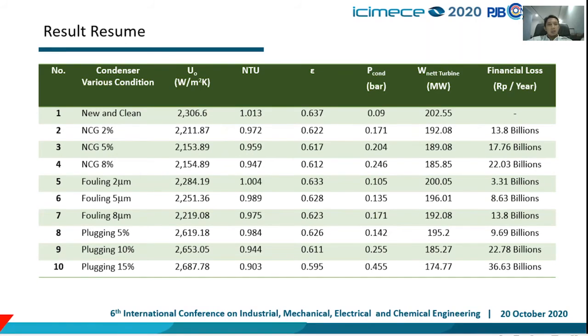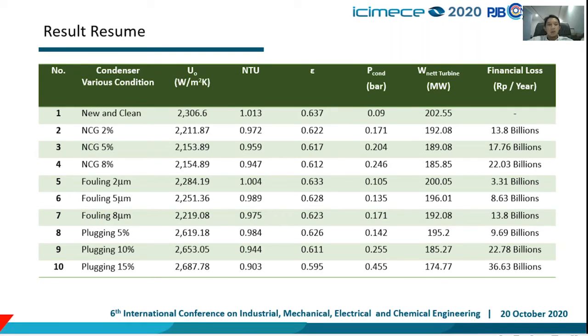Here are the results of this study showing variation from new-and-clean, non-condensable gas, fouling, and plugging conditions. In the new-and-clean condition, the power output of the turbine is 202 MW. In the non-condensable gas condition at 8%, the turbine power output decreased to 185 MW. In the plugging condition at 15%, the turbine power output decreased to 174 MW.